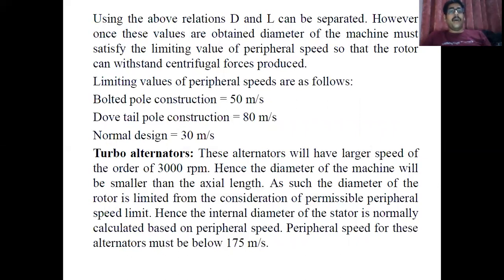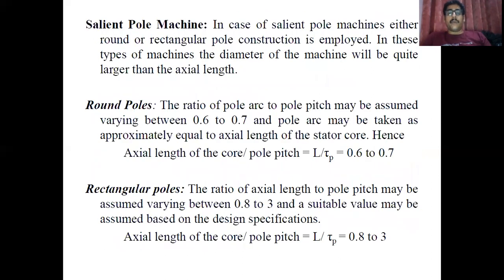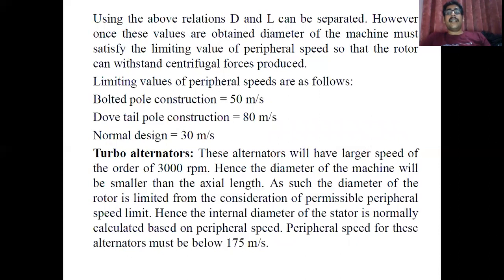Using the above relation, the diameter and stator core length are obtained. However, if in a numerical problem the peripheral speed is given, then separation of D and L cannot use the previous formula L/τp. Instead, you use the formula for peripheral speed, which has certain limiting values depending on machine type. For bolted pole construction, peripheral speed should not exceed 50 m/s; for dovetail pole, not greater than 80 m/s. In general, for a synchronous machine, peripheral speed should not exceed 30 m/s.